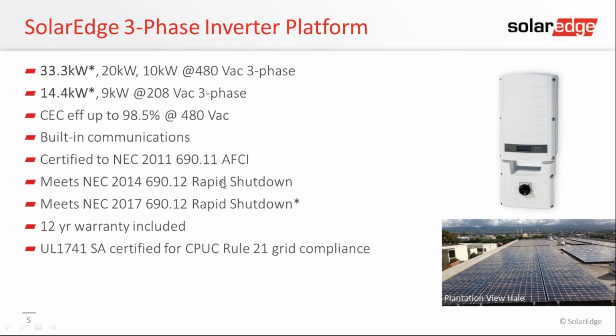690.12 talks about rapid shutdown, basically bringing your rooftop voltage to less than 30 volts within 10 seconds. I believe, and I could be wrong about this, that the Canadian Electrical Code adopted that same requirement in 2015. And then again, please someone chime in on the chat feature if it was in 2015 or if it's going to be this year in 2018. No, that's correct. It's already implemented. Okay, good. Thank you for the note.